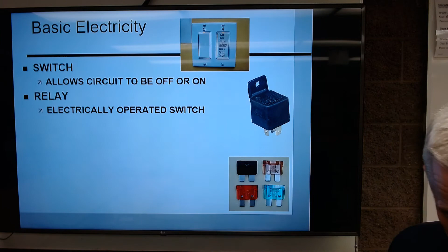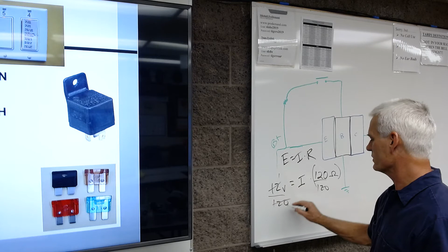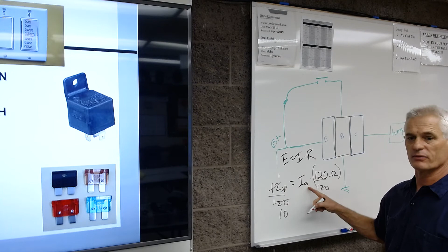So if I look over here on the whiteboard, I know that E equals IR, which means—remember, E is voltage, I is current, R is resistance. So voltage equals current times resistance. Let's say I've got a 12-volt circuit from the battery, and a 120 ohm coil in my relay. If I divide each side by 120, this is going to be 1/10. So I've got 1/10 of an amp flowing through that control circuit.